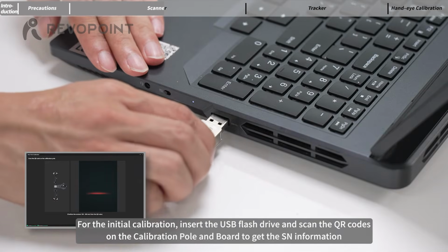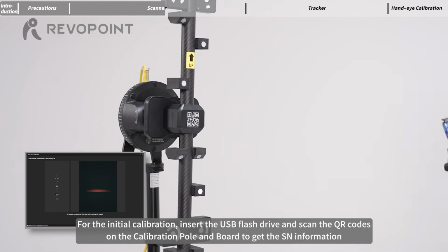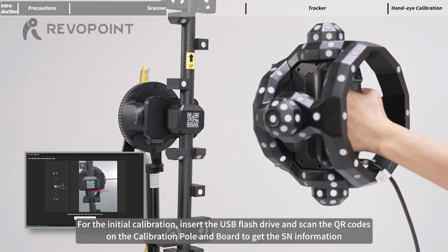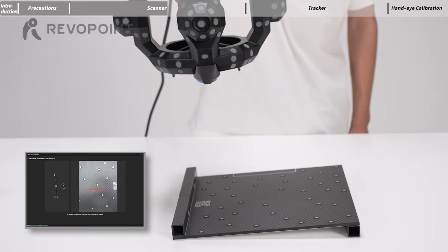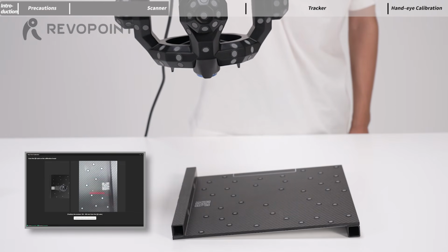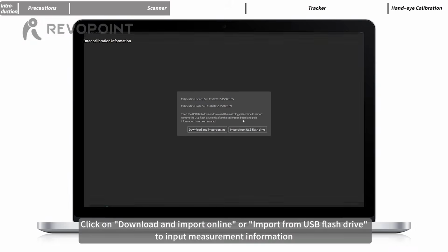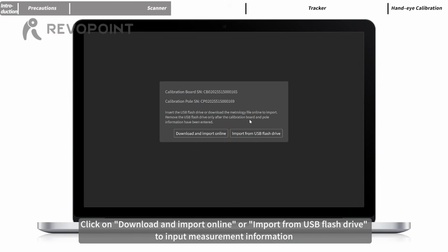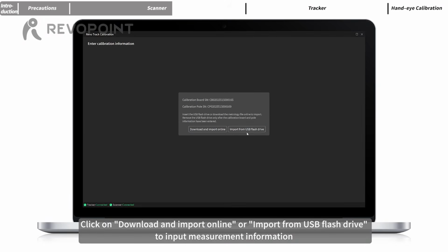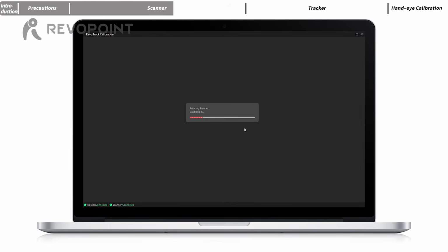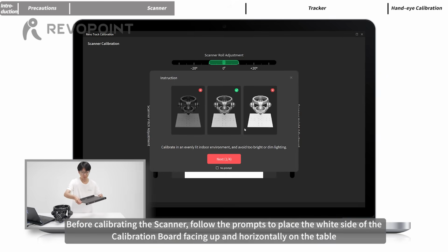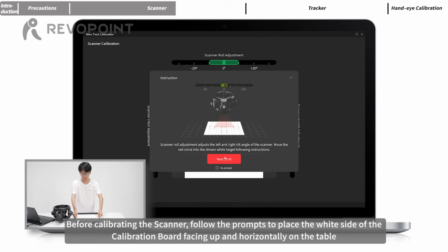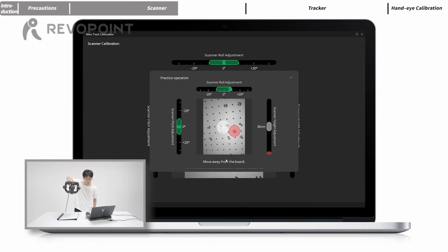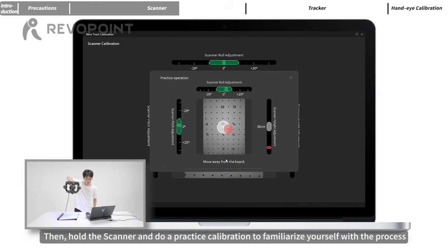For the initial calibration, insert the USB flash drive and scan the QR codes on the calibration pole and board to get the SN information. Click Download and Import Online or Import from USB flash drive to input measurement information. Before calibrating the scanner, follow the prompts to place the white side of the calibration board facing up and horizontally on the table. Then, hold the scanner and do a practice calibration to familiarize yourself with the process.